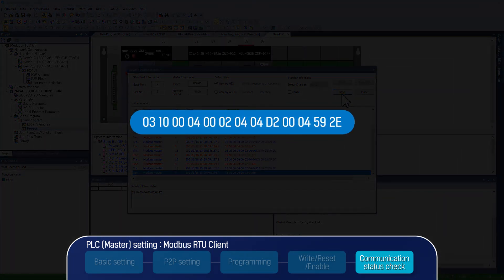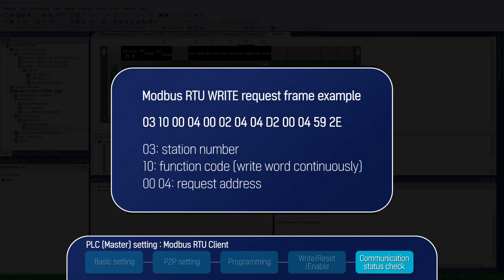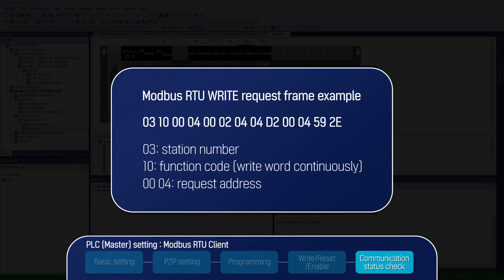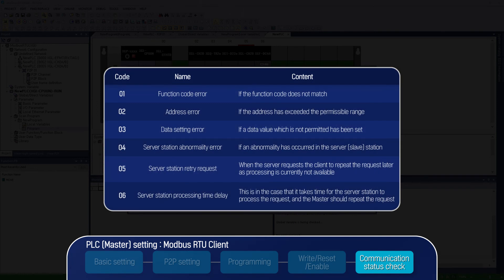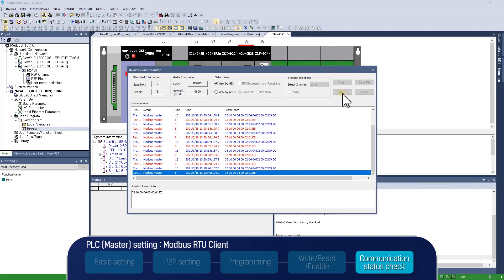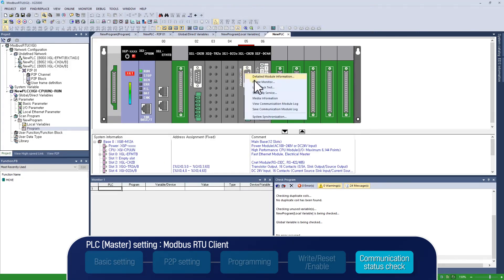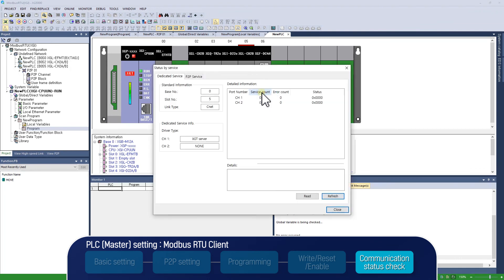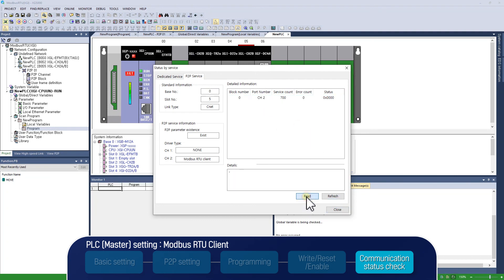Here's a brief explanation on Modbus RTU write request frame in hexadecimal. The first 03 is the drive station number. The next 10 is function code 16, write multiple command. 0004 is the Modbus address for reference frequency. For more information, please refer to the drive user's manual. In case of a communication error, we will see the detail from an error code. The response frame format when an error occurs begins with an 8-0 followed by the station number and an error code. We can monitor the communication status selecting Status by Service in System Diagnosis, and find the actual communication and error count in P2P Service tab.